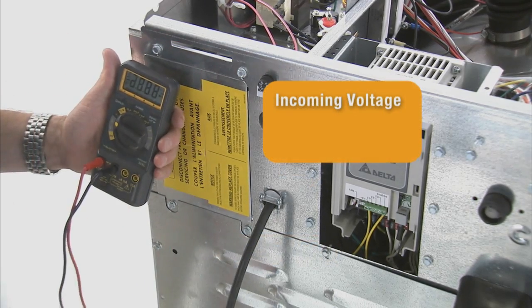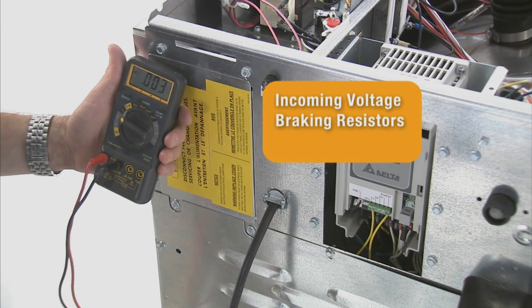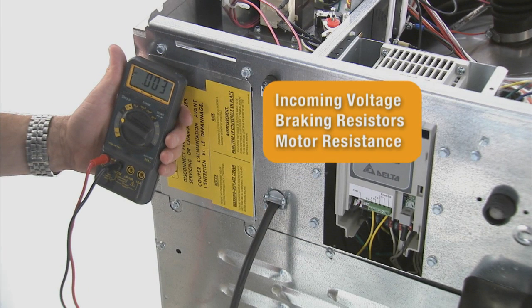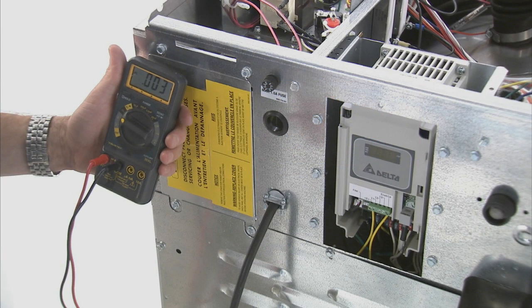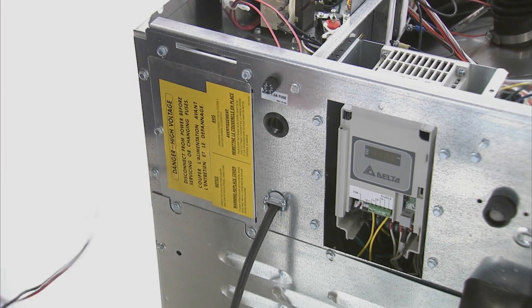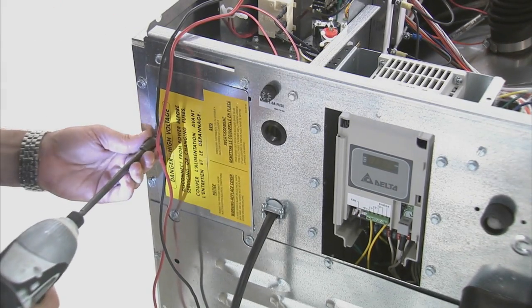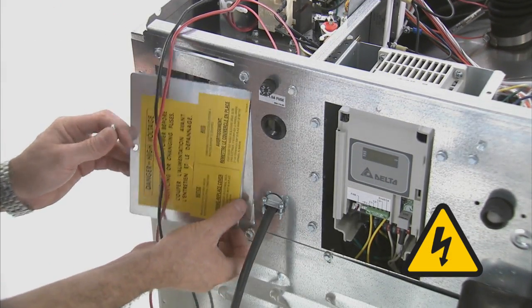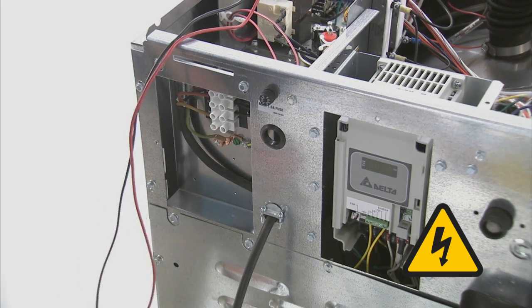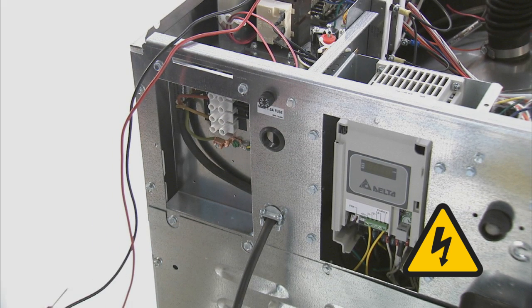These are the incoming voltage, the braking resistors, and the motor resistance. All 3 of these steps will require the use of a voltmeter. The first step is to check the incoming voltage to the machine. L1 and L2 should each have approximately 120 volts present. Remove the protective cover to access the incoming terminal block.